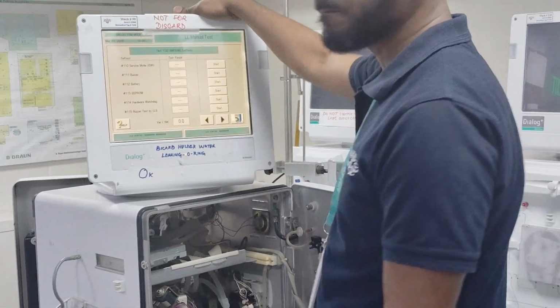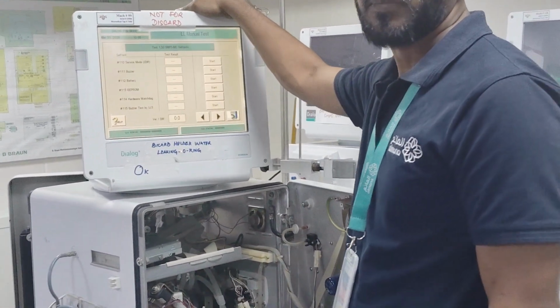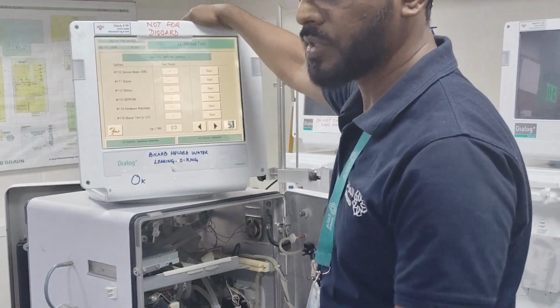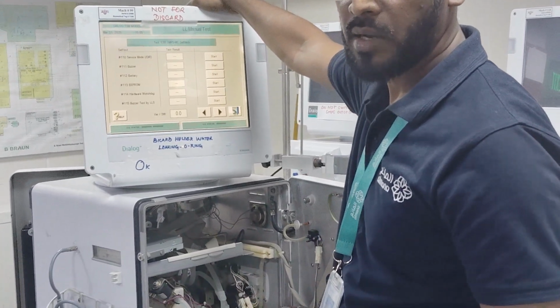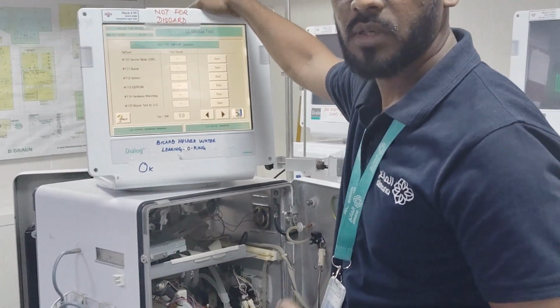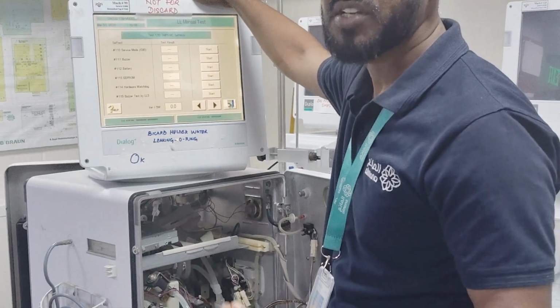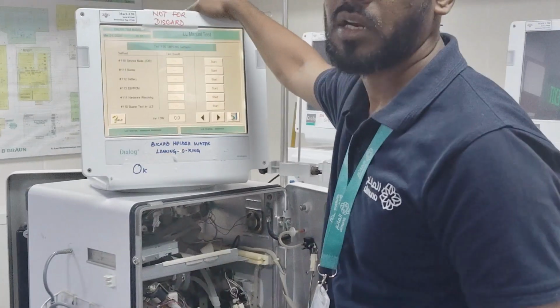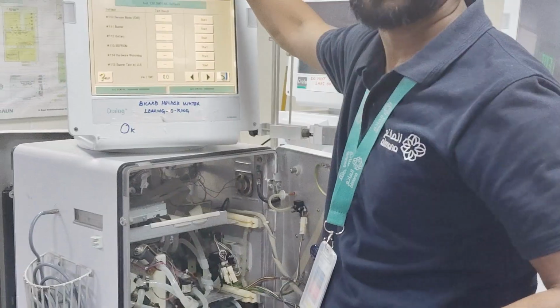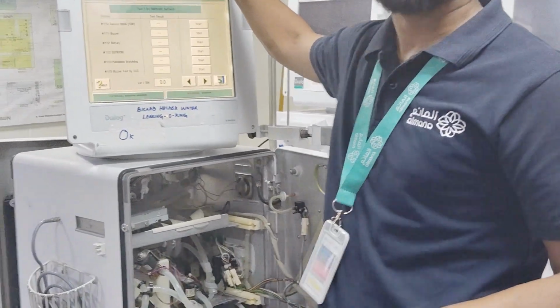This option will be used in the therapy mode. Or, no, it's not therapy mode. In any mode, we can just use our instrument to check it. We'll use it for patient leakage current. For that, they have to connect the safety analyzer. The safety analyzer is there.